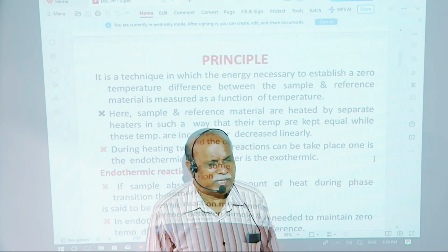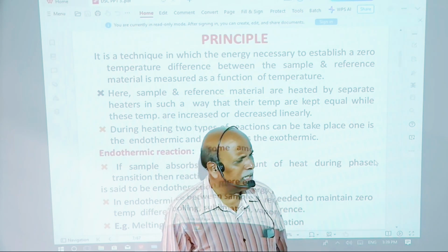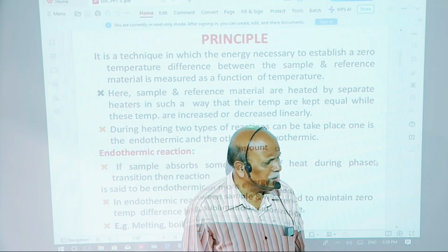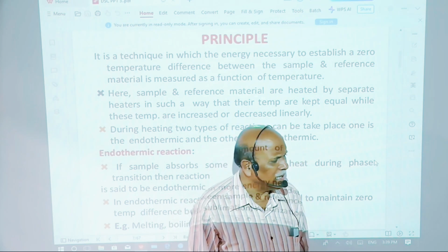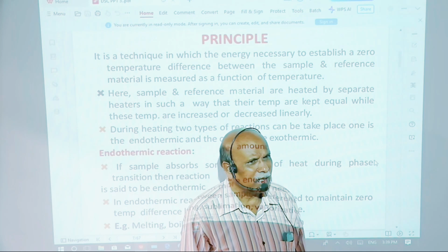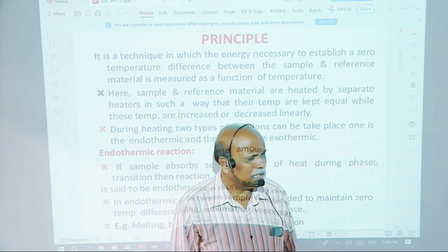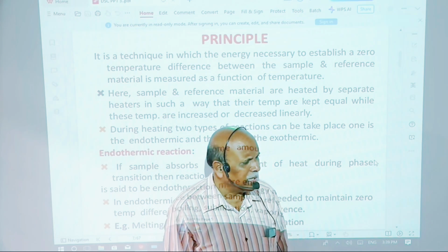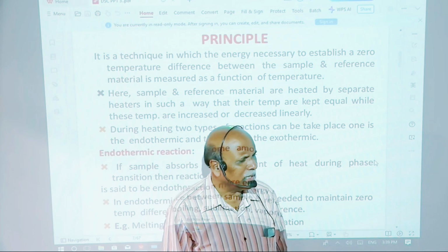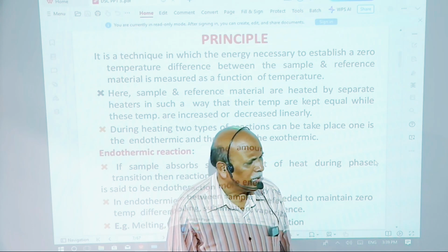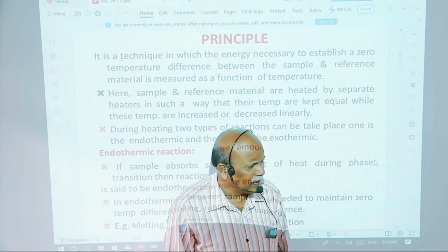The principle of DSC: it is a technique in which the energy necessary to establish a zero temperature difference between the sample and reference material is measured as a function of temperature. The sample and reference material are heated by separate heaters, in which the temperatures are kept equal while the temperature is increased or decreased linearly.